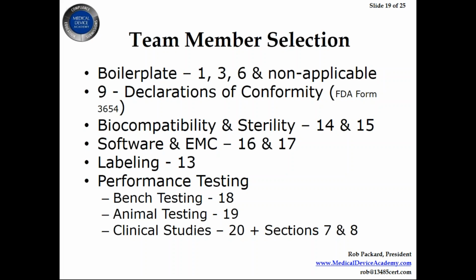For biocompatibility and sterility, that's section 14 and 15 of your 510K submission, and you really should have somebody with a microbiology background doing that. I'm an example, but I work with a lot of people that know even more than I do about that, and they help with filling out those sections.